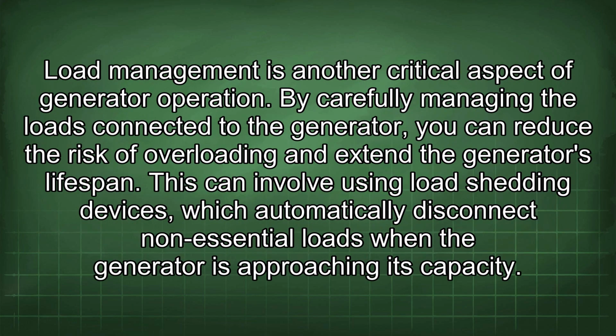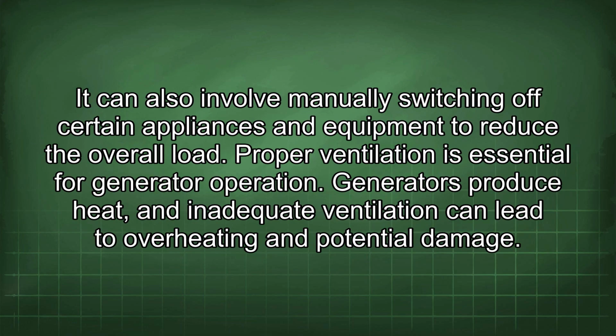Load management is another critical aspect of generator operation. By carefully managing the loads connected to the generator, you can reduce the risk of overloading and extend the generator's lifespan. This can involve using load-shedding devices, which automatically disconnect non-essential loads when the generator is approaching its capacity. It can also involve manually switching off certain appliances and equipment to reduce the overall load.